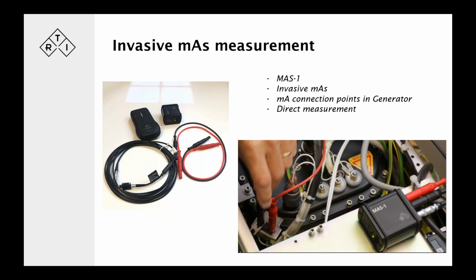And then with the MAS1, this is what happens here. You plug it into your generator, you get the jumper disconnected, and you're actually measuring the real true mA value. And then again, these cables go to the generator, and this cable right there is connected to the Piranha or the Cobia.